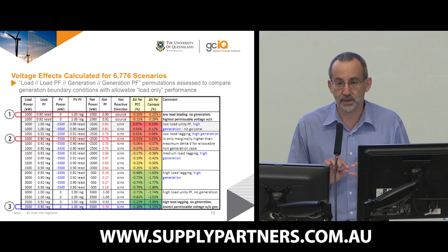One of the first things we did was a lot of calculations to look at the expected changes in voltage on the campus for different configurations or conditions on site - different loads, different generation, different power factors, the sort of things that might bother them. The reality was that even with solar, there really wasn't much change compared to no solar at all. We were quite confident that even on that piece of rural network, we weren't going to have too many problems maintaining the voltage on the network.